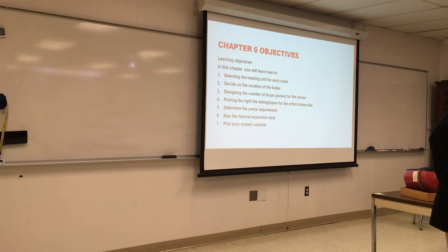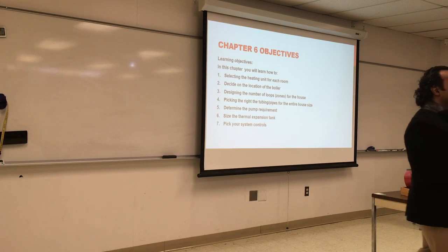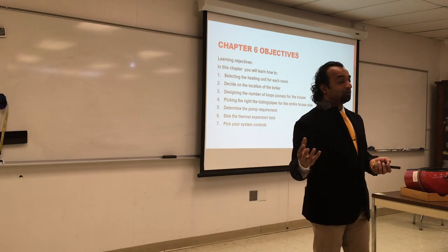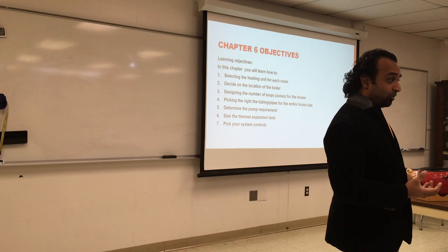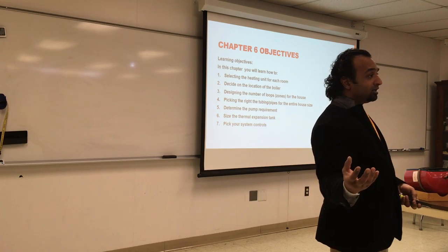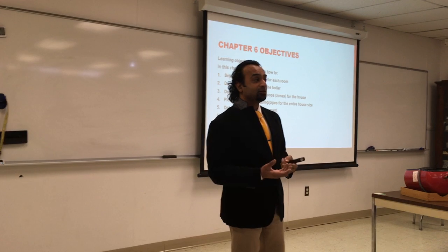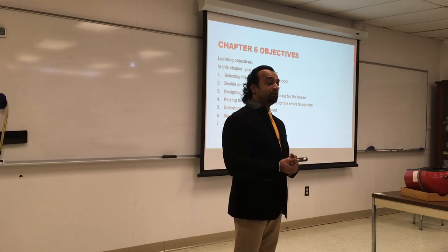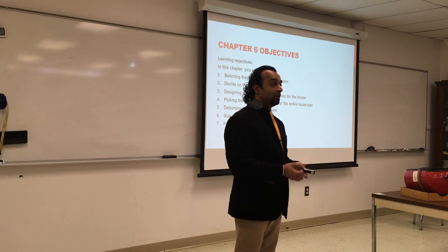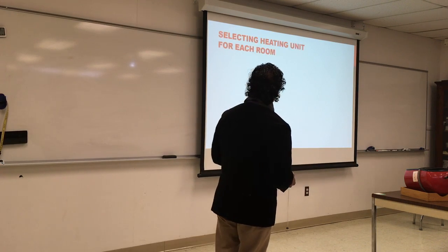You don't want to put it next to the stove. You don't want to put an incandescent light next to the thermostat, because it will over-read the temperature. You don't want to put it in a place that's very far, because then you're going to get overheated in one part until the heat gets over there. And that also gives you an idea where you will put your thermostat in your design project. Okay?